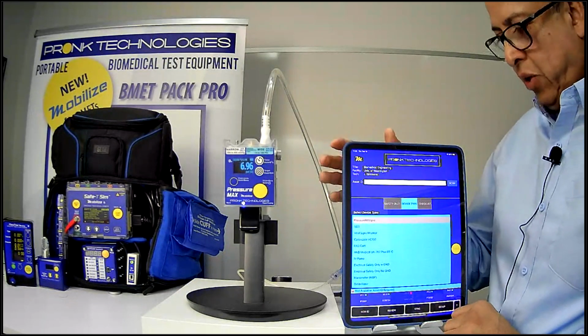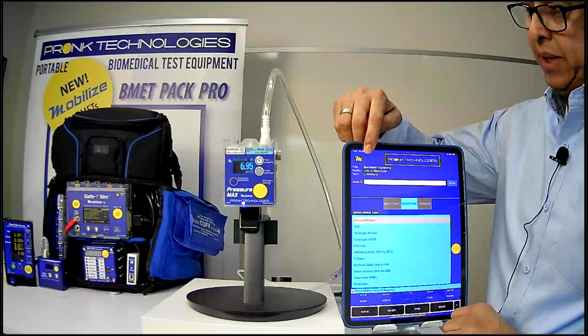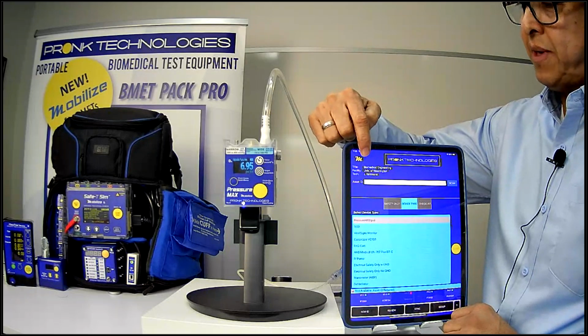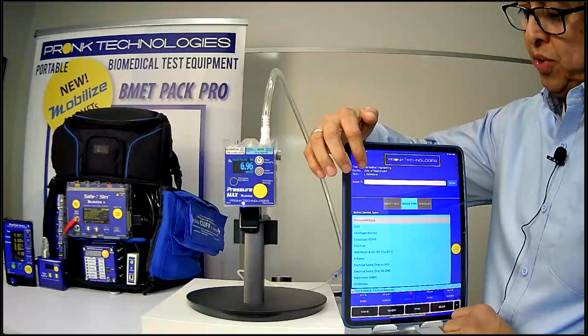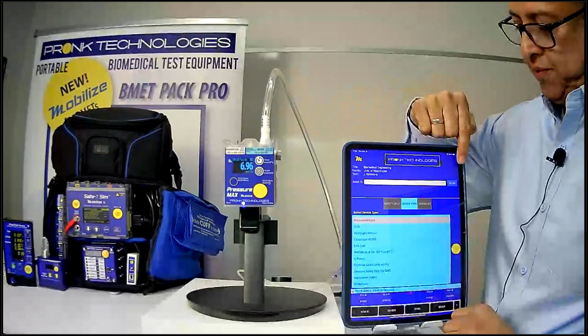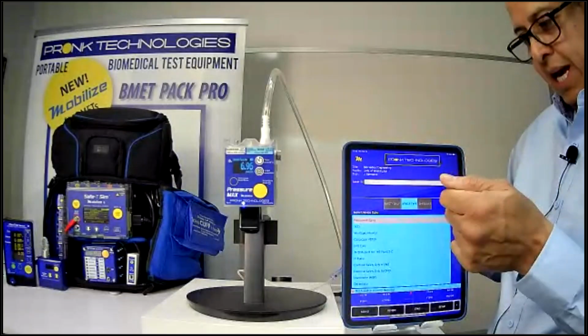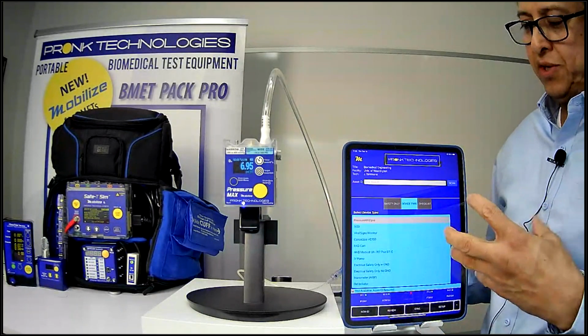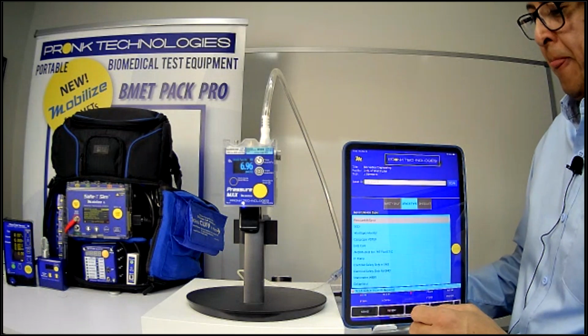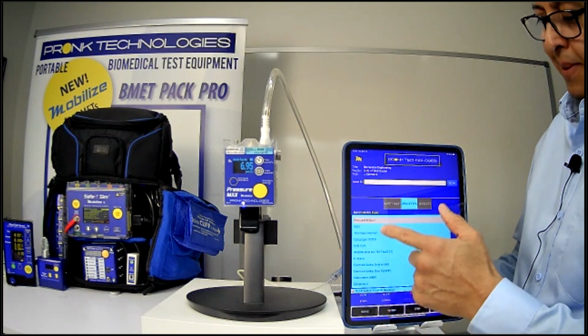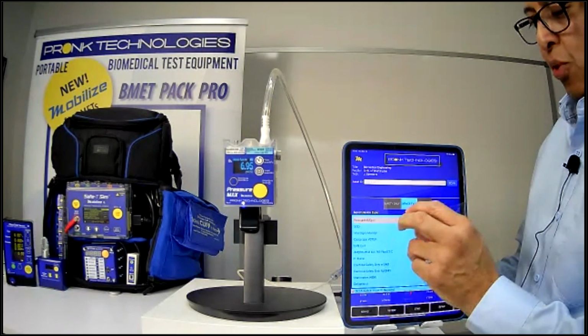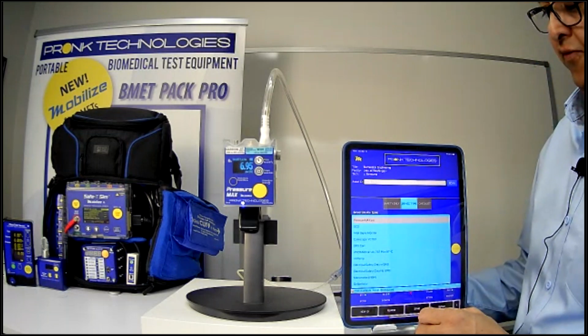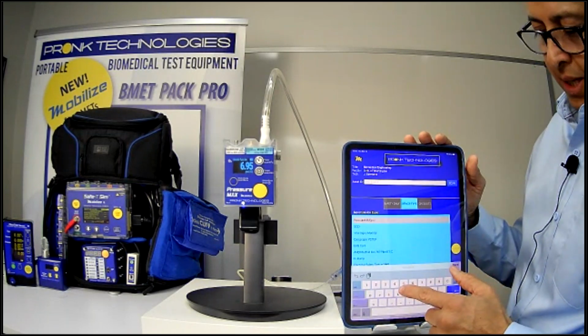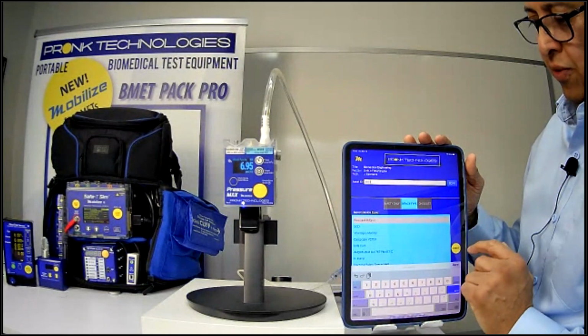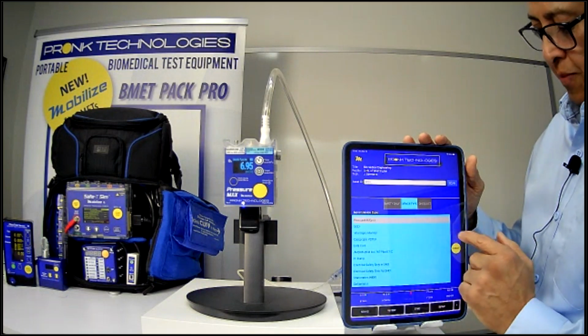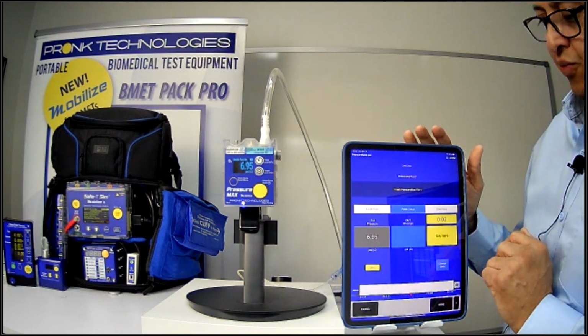So just a quick overview of the app itself. You have the ability to customize the header information here at the top in the setup menu. You can enter in an asset ID, or you can use the scan function to scan the barcode on the medical device to enter that asset ID into the report. And then you have the ability to pick a sequence of protocols that you've designed under the app itself. So I'm going to go ahead and enter in an asset ID here, and I'm just going to select Pressure Max here so you can kind of see how this would work.